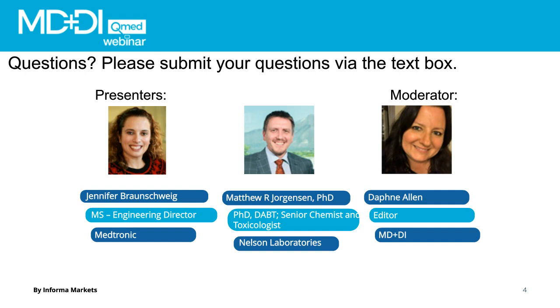Now, to justify it, I wouldn't really point to a specific biological test. Rather, what I would do is point to chemistry and a toxicological risk assessment. So if you do an extractables study on the device that contains a CMR and you detect that CMR at a certain amount, then a toxicologist can claim conclusively whether or not that amount actually could be harmful to a person or not.